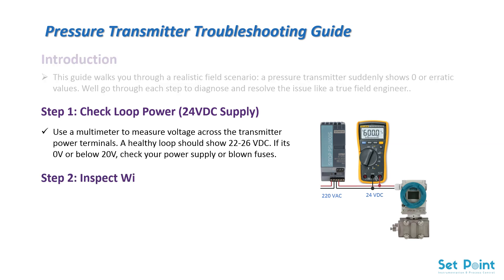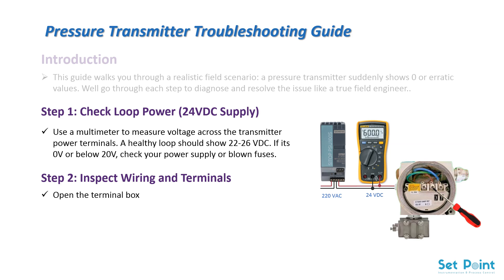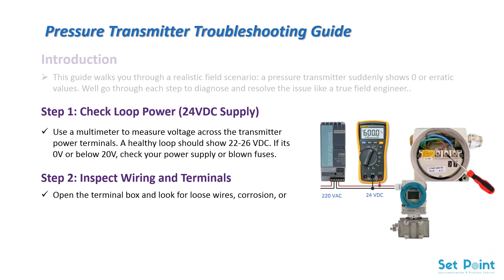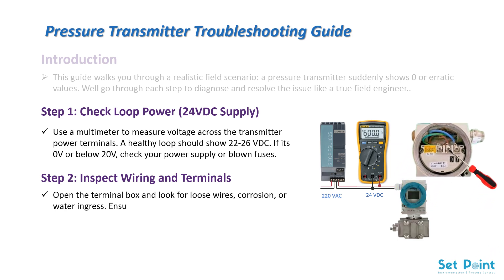Step 2: Inspect wiring and terminals. Open the terminal box and look for loose wires, corrosion, or water ingress. Ensure terminal screws are tight. Reterminate if necessary and ensure polarity is correct.